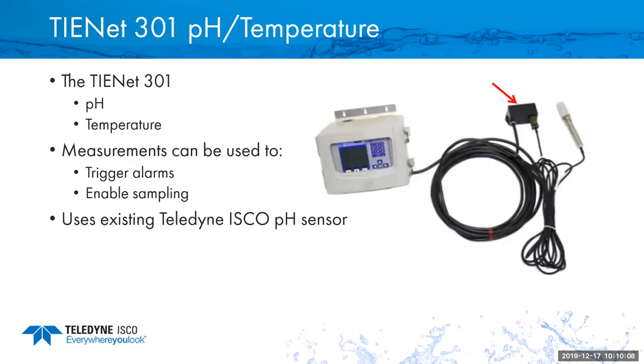Now, in depth, the 301 pH sensor, it looks like this. It's got a little box, and then you attach your pH probe, so you can change the pH probe out over time as it's warranted in your application. So the 301 measures pH and temperature and logs that information in the signature meter. It can also be used to trigger alarms and enable sampling. It uses our existing pH sensor from all of our other meters that we've had, either the 6712 or the old 4200s. So it uses the exact same pH sensor.